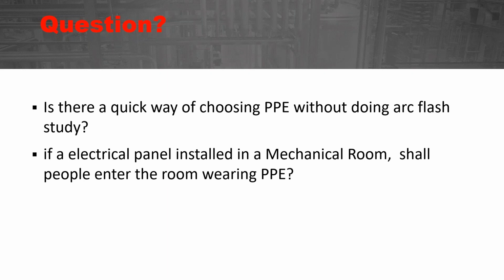And for the ones of you that are familiar with 70E and its progression over the years, you will remember we used to have a category 0. Category 0, 1, 2, 3, 4. In fact, even a while before that, we had a category 2 star or 2 asterisk. That category 0 was there, and just turning on a breaker, turning off a breaker, turning on a safety switch or disconnect switch, we had to wear category 0 clothing.